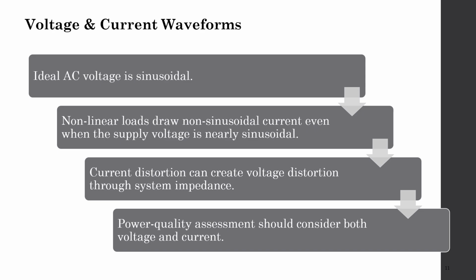Then voltage and current waveforms. When we talk about this, ideal AC voltage is sinusoidal. Nonlinear loads draw non-sinusoidal current even when the supply voltage is nearly sinusoidal. Current distortion can create voltage distortion through the system impedance. Power quality assessment should consider both voltage and current.